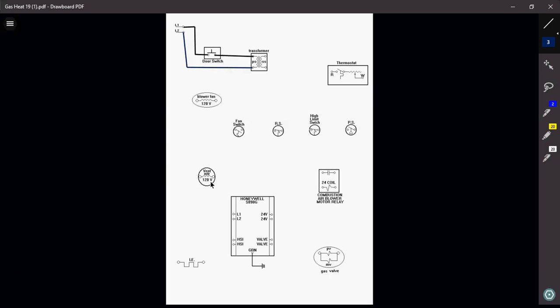We have a fan switch. Our fan switch is a temperature actuated switch. There's the thermostat, right? It's a thermostatically activated switch. So as temperature rises, as it goes up, that switch will close. I want my fan switch to be the switch that's going to control my blower fan. So how do I do that?